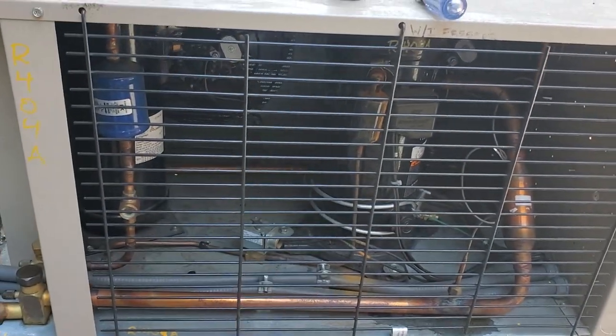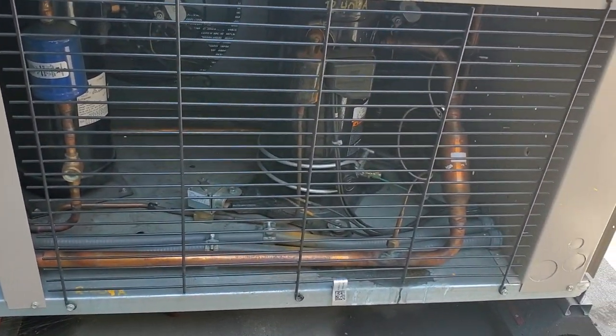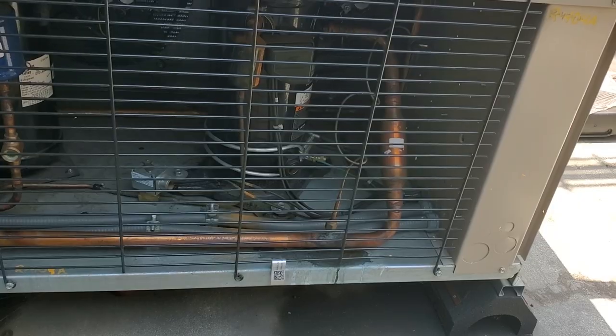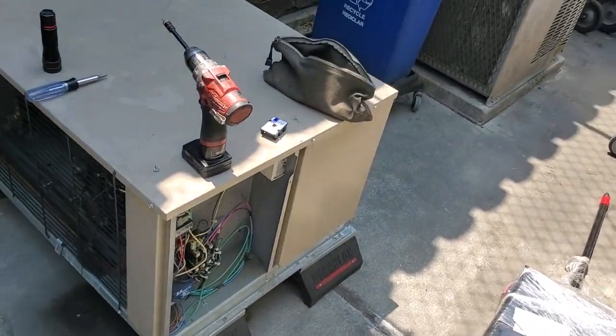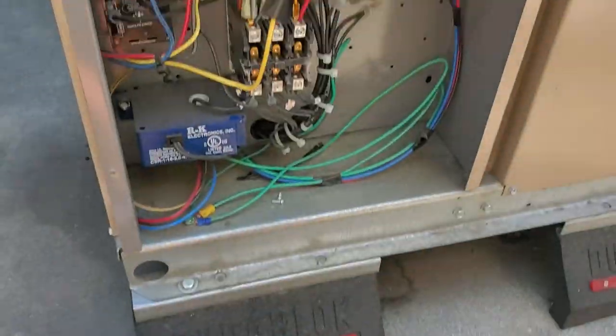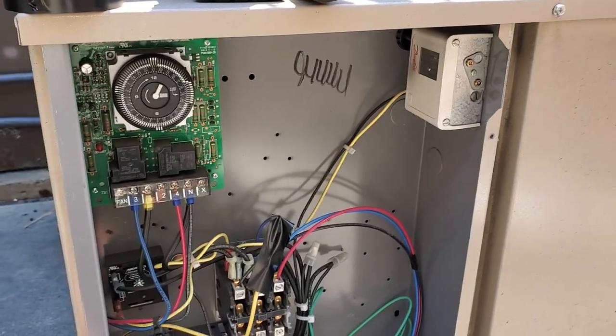I just did a visual inspection in the condensing unit. I don't see anything wrong. I don't see any rub outs on the wires. I'm going to let this thing keep running and defrost. I don't see any reason for this breaker to trip yet besides that contactor. I had to go to the supply house to get the right contactor — one with lugs. And I just checked on it: it's almost completely thawed out, so I probably won't even have to get my hoses out.